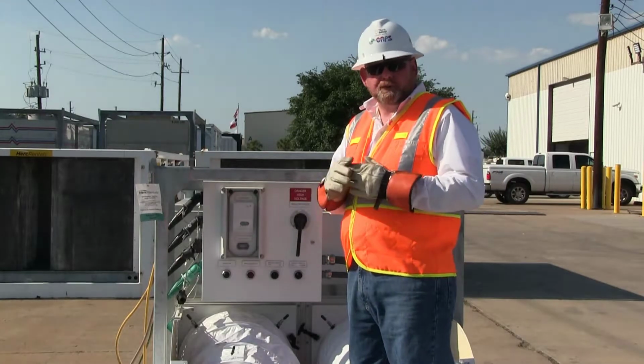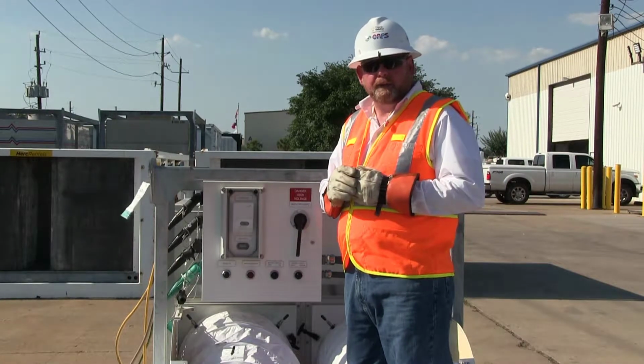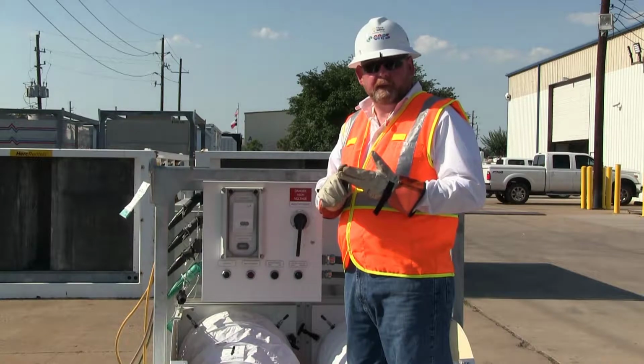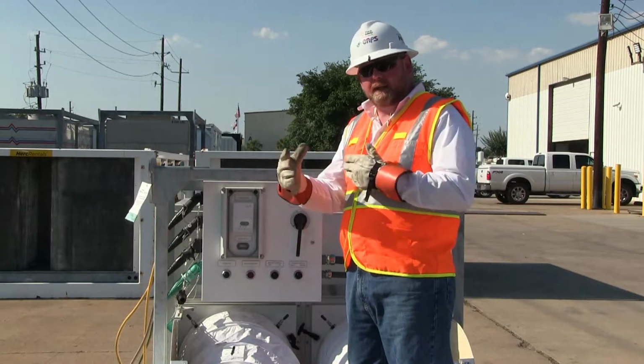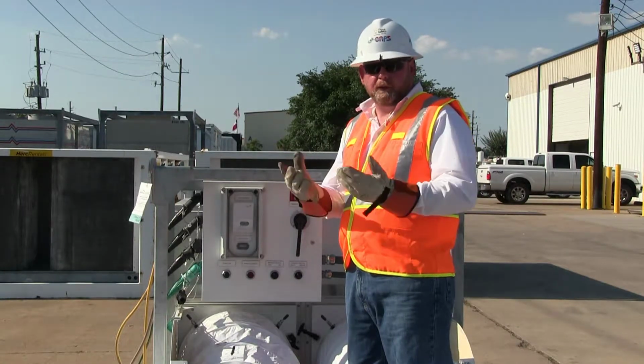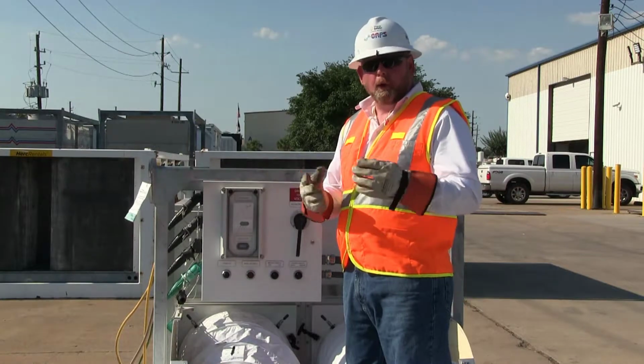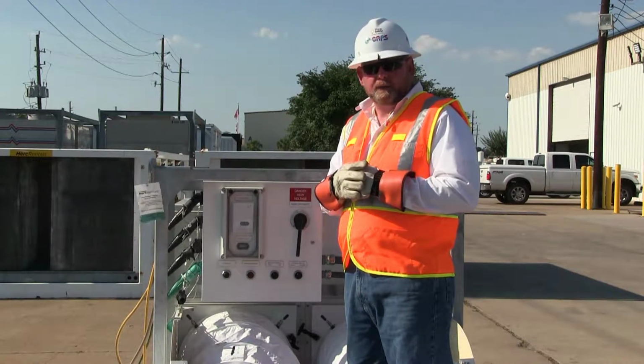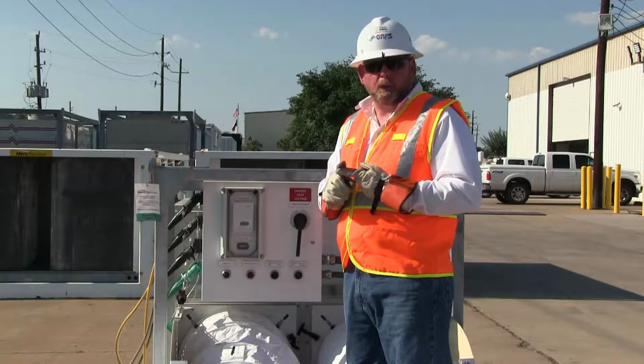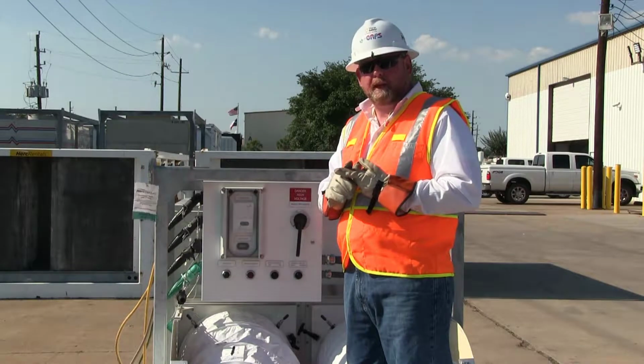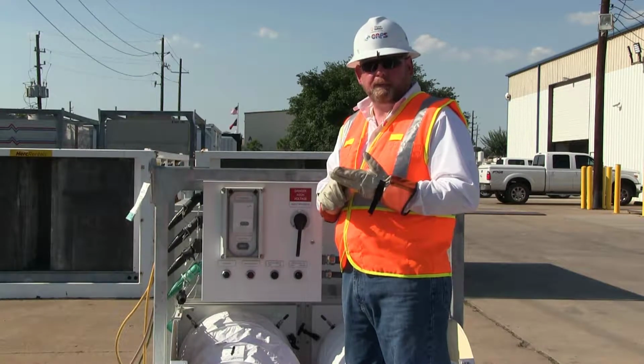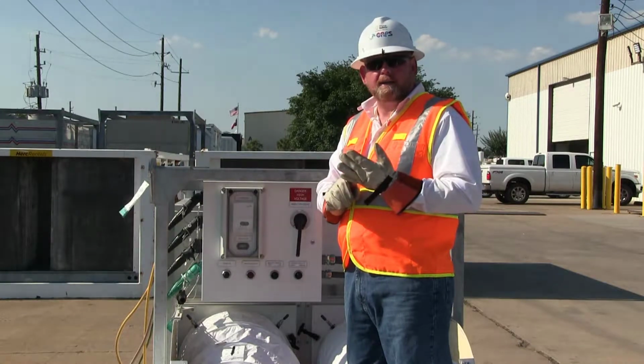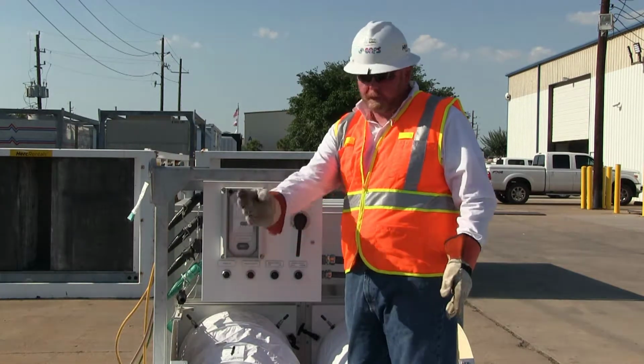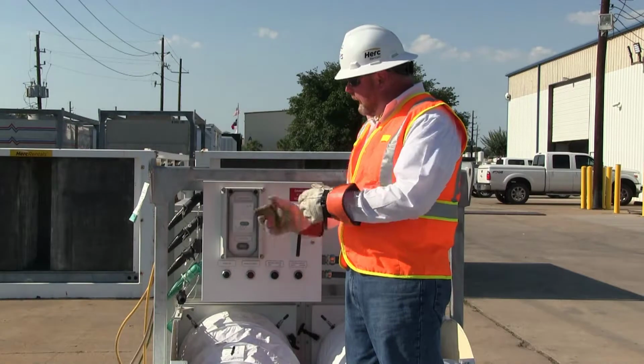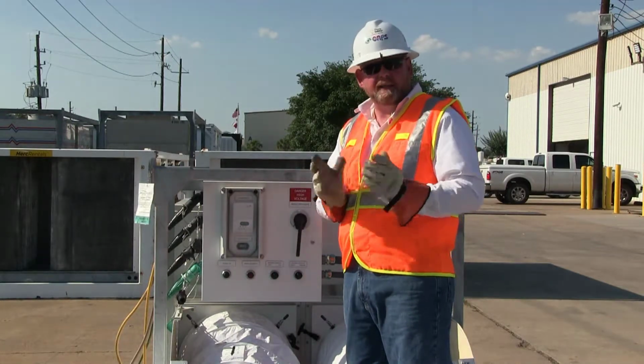Okay, to recap our setup of our 5-ton package unit that's capable of heating, cooling, or dehumidification, we started out by setting it, placing it to the location using a fork truck or crane, or potentially could even use the integrated casters. Secondly, we checked our power requirements for the job, particular application, be cooling, heating, or dehumidification. Then we primed our condensate trap. We hooked up our ductwork, supply and return. We've got all of our power hooked up. We verified that the phase is correct.